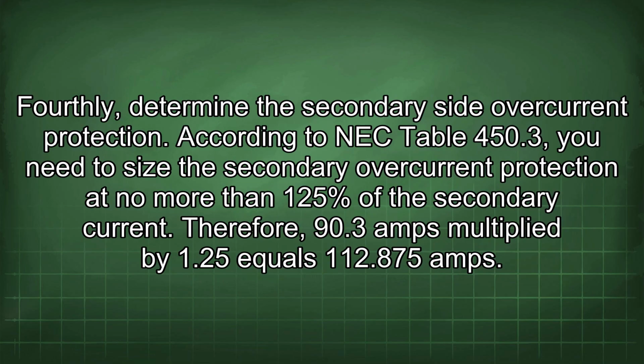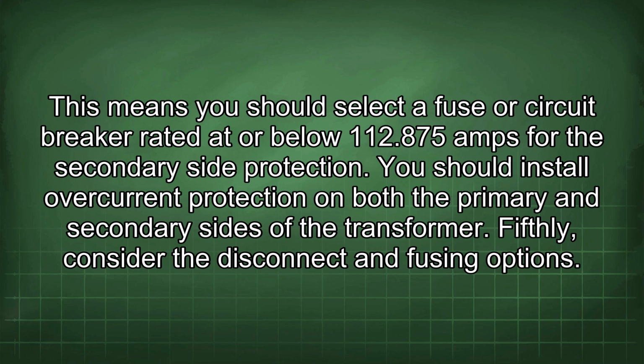Fourthly, determine the secondary side overcurrent protection. According to NEC Table 450.3, you need to size the secondary overcurrent protection at no more than 125% of the secondary current. Therefore, 90.3 amps multiplied by 1.25 equals 112.875 amps. This means you should select a fuse or circuit breaker rated at or below 112.875 amps for the secondary side protection. You should install overcurrent protection on both the primary and secondary sides of the transformer.